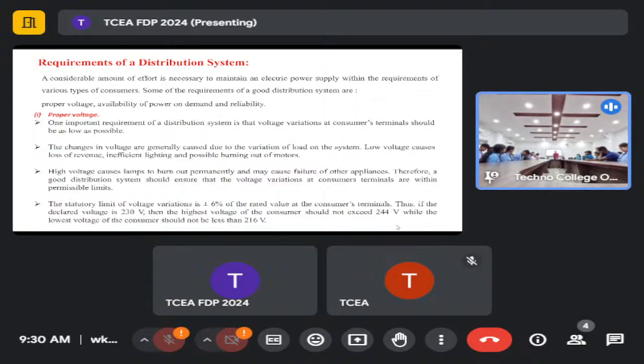Now, in the case of a motor, what will happen? The motor will always try to maintain its horsepower, and it will draw more current from the system, and eventually it will burn. That is the difference between resistive load and motor. If the voltage is less in a light, power will be less, illumination will be less. But if the voltage is less in a motor, the motor will try to give the required torque. So it will draw more current from the system, and in the process it will burn. Power factor plays a very important role.